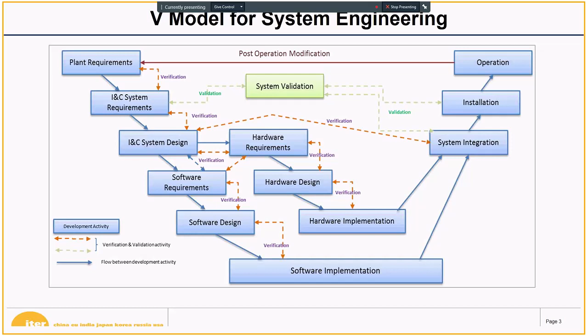So verification is mainly about, are we building the product right? We check that the requirements are met, and we perform this during development. It's component and subsystem centric, because it usually does not talk about the system as a whole, but whether each component meets its requirements. Verification methods, which are very important, can be inspection and analysis, or acceptance testing, or engineering review.